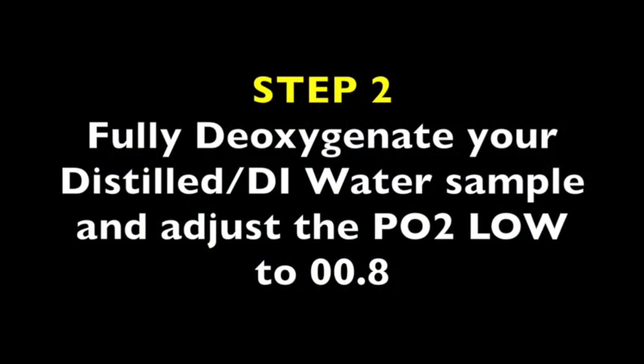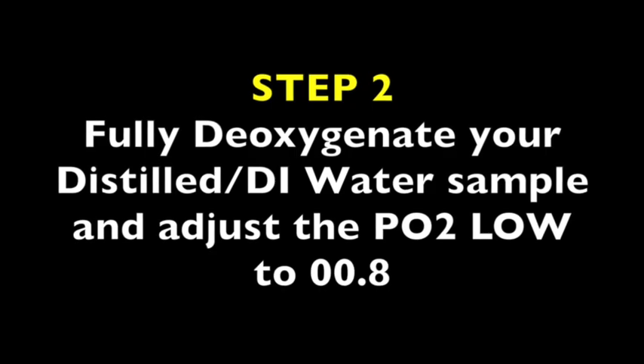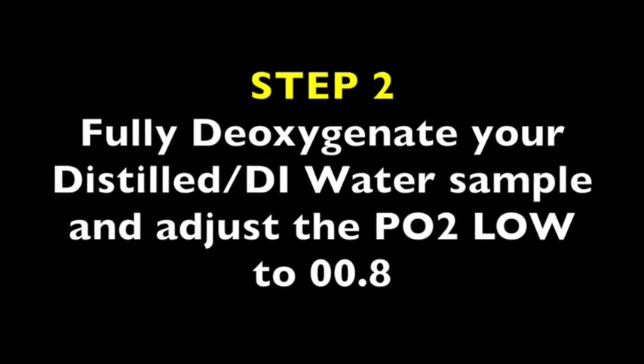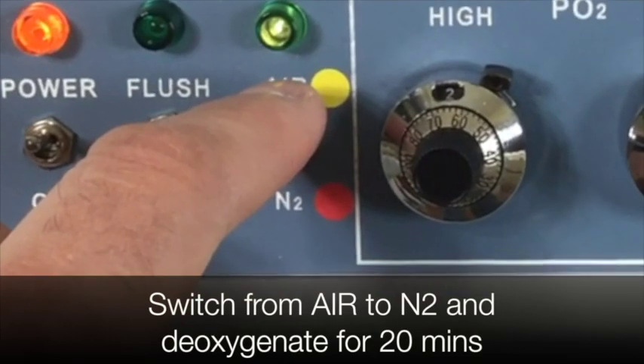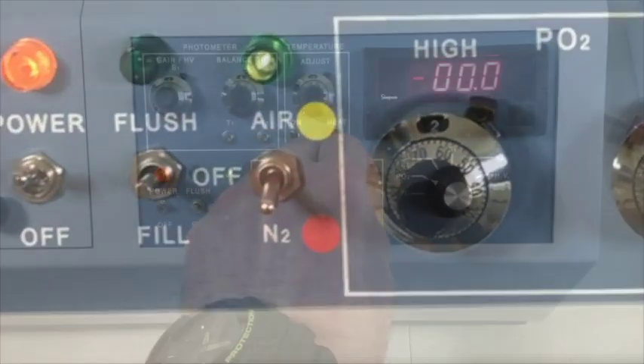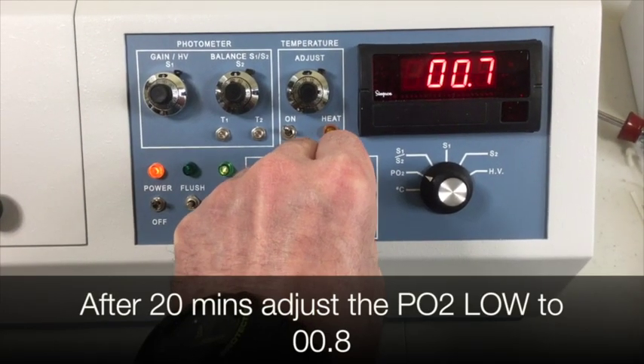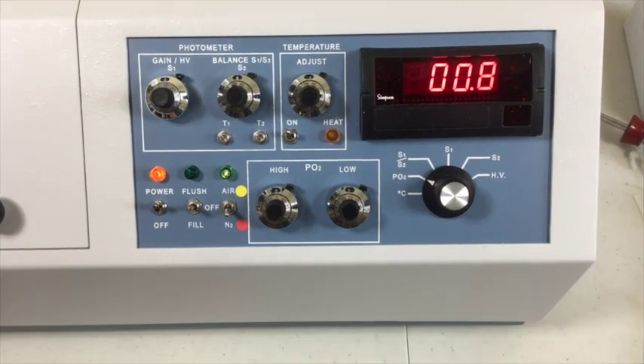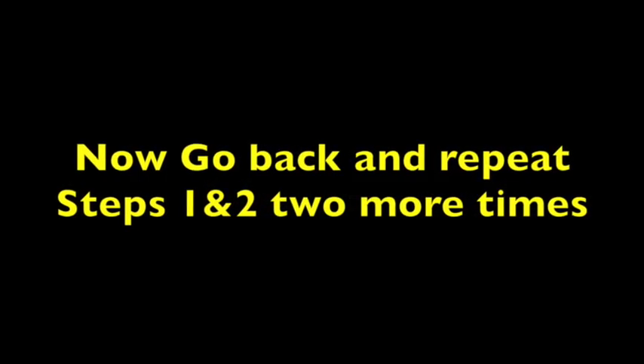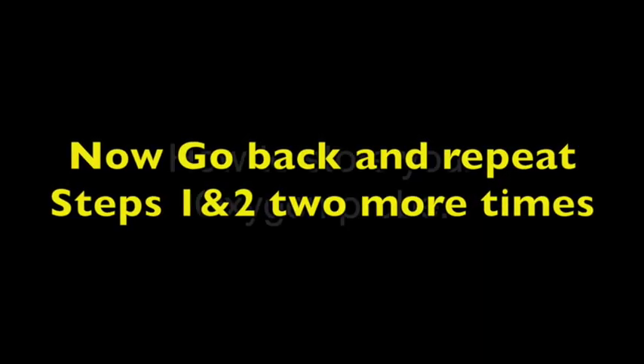Step 2. Fully deoxygenate your distilled or DI water sample and adjust the PO2 low to 0.8. Switch from air to nitrogen and deoxygenate for 20 minutes. After 20 minutes, adjust the PO2 low to 0.8. Now go back and repeat steps 1 and 2 two more times.